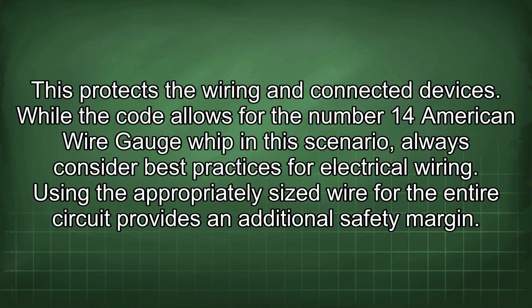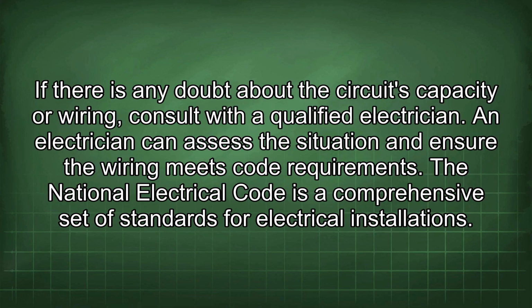While the code allows for the number 14 American wire gauge whip in this scenario, always consider best practices for electrical wiring. Using the appropriately sized wire for the entire circuit provides an additional safety margin. If there is any doubt about the circuit's capacity or wiring, consult with a qualified electrician. An electrician can assess the situation and ensure the wiring meets code requirements.